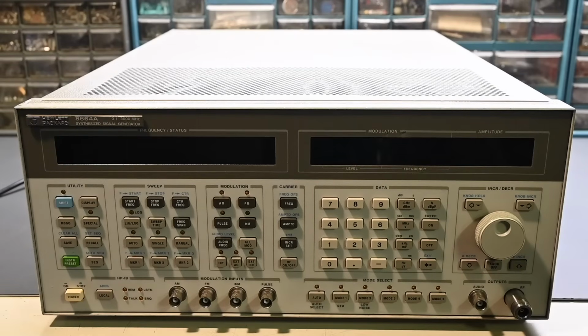The output is rated from 100 kilohertz to 3 gigahertz with a 10 millihertz resolution, or 0.01 hertz, which is a very impressive specification. But to take full advantage of the 10 millihertz steps, you need a very accurate and stable time base. So this instrument is equipped with option 1, which is a high stability time base option, so we should be able to take full advantage of the 10 millihertz resolution.